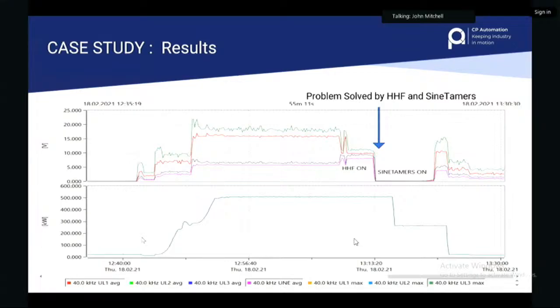So what we did was run the drives up—this is power for the drives. You can see the super harmonic noise getting louder as the power went up. We switched the HHF on and then off again, just to see how it did, then turned it back on. It got us about halfway, which was a pretty good result since it was only dealing with one set of the problem.